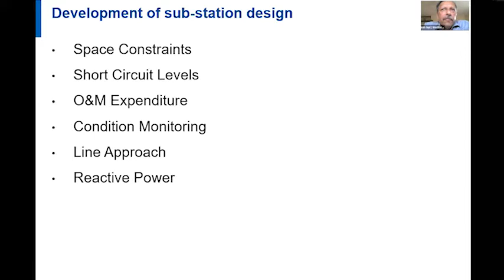The other factor is reactive power. Today, with a large network of 765 and 400 kV in this country, at nighttime when the load is very low, some regions have severe overvoltages. The only option to control those overvoltages is to switch off lines, which in an emergency could adversely impact the grid.